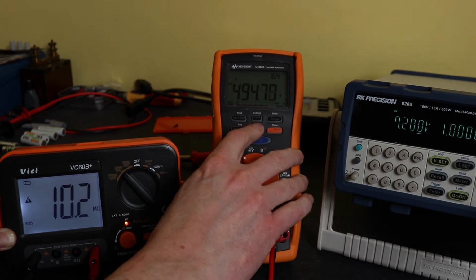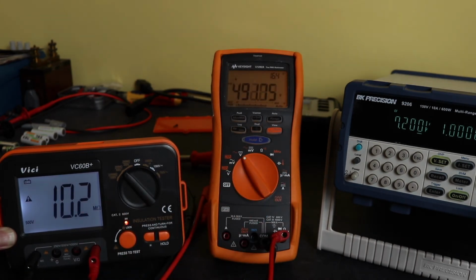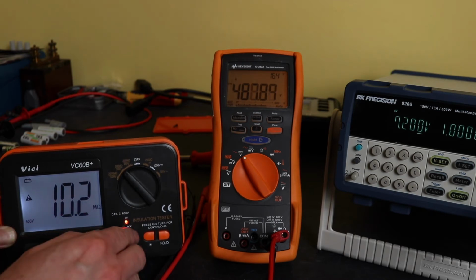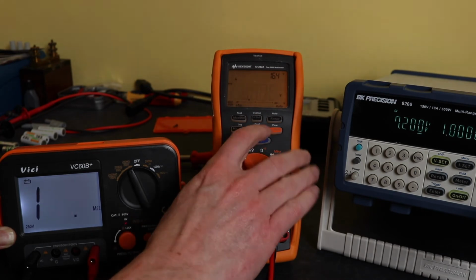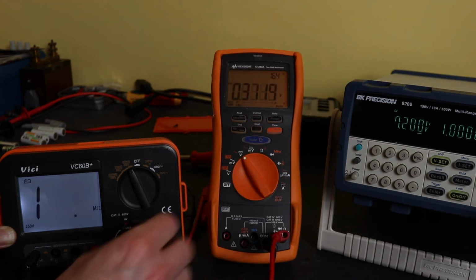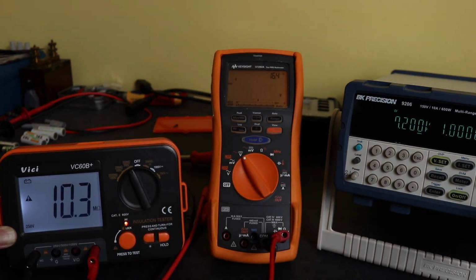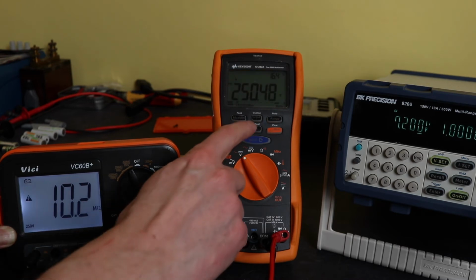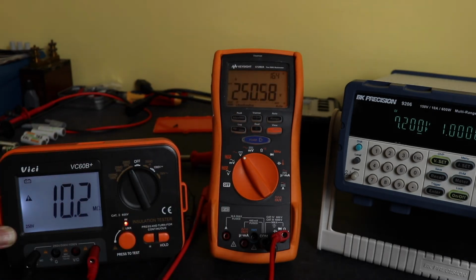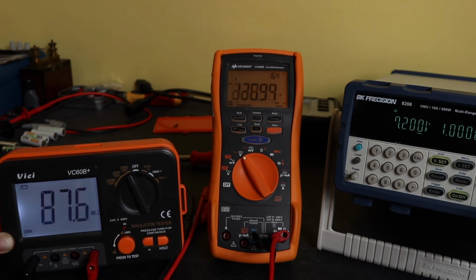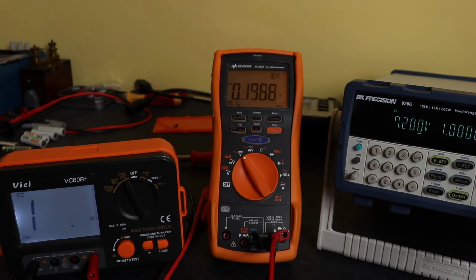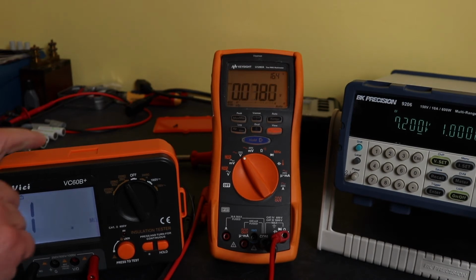So I should turn the light on, shouldn't I? Now down to 491 volts, 490 volts. It's actually going the other way instead of slowly rising, it's decreasing. Now, and if I 250 volts, isn't it? Sorry. So 250 volts just creeps over, which is not good. As I said, the IEC standard requires the voltage to always be above the nominal test value.